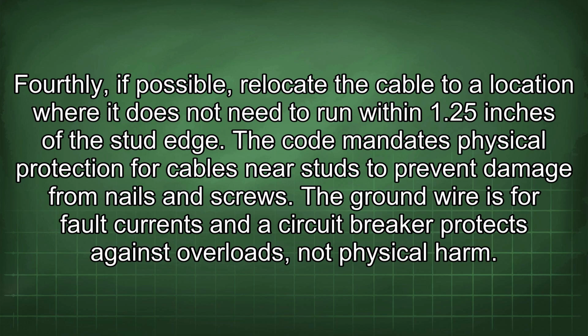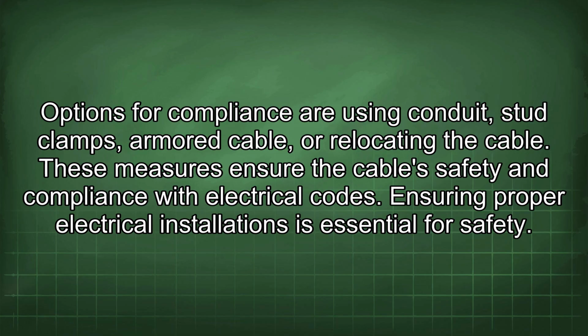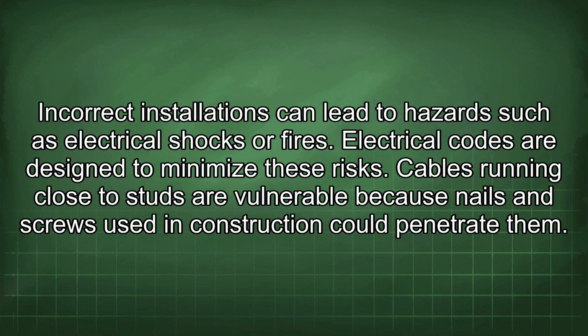The ground wire is for fault currents and the circuit breaker protects against overloads, not physical harm. Options for compliance are using conduit, stud clamps, armored cable, or relocating the cable. These measures ensure the cable's safety and compliance with electrical codes. Ensuring proper electrical installations is essential for safety. Incorrect installations can lead to hazards such as electrical shocks or fires. Electrical codes are designed to minimize these risks.